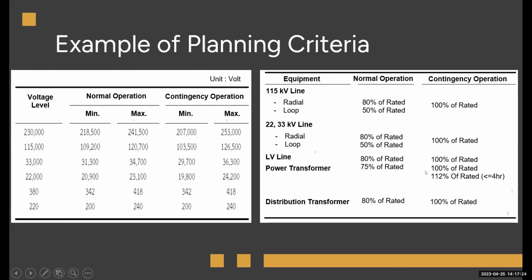For the power transformer it is 75% of rated. This is the decision point at which we create a new project. Take an existing substation with one power transformer rated 50 MVA. If the load reaches 75% of 50 MVA, that means we need a project to expand this substation, maybe install another power transformer, or construct a new substation to receive some load from the existing power transformer, something like that. We use this criteria to make our decision.